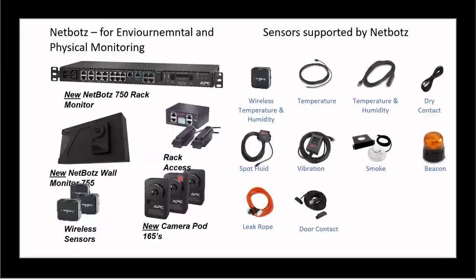Then there are cameras and wireless sensors: a temperature sensor to check if the temperature is fine, a humidity sensor, dry contact to check the air, and sensors for leakage, vibration, and smoke. This is a beacon, which gives alerts. These sensors connect to this unit, which connects to the network of the data center, and the data center manager can see everything happening inside the data center through the NetBotz.